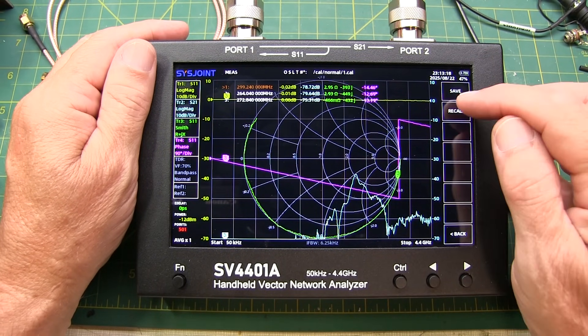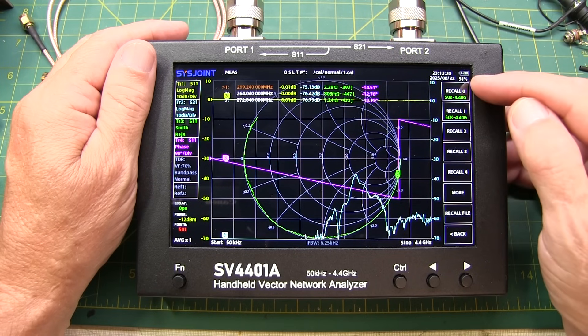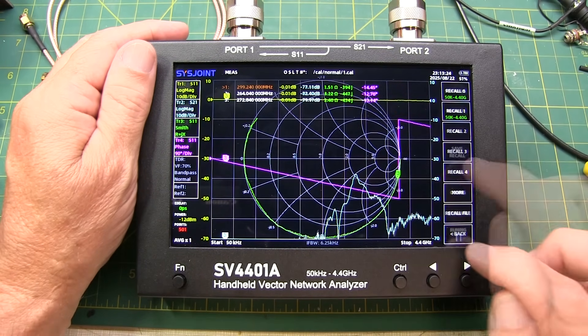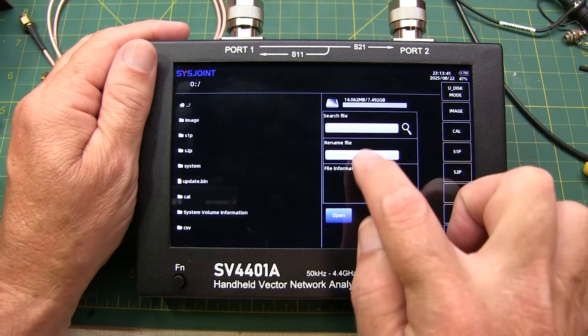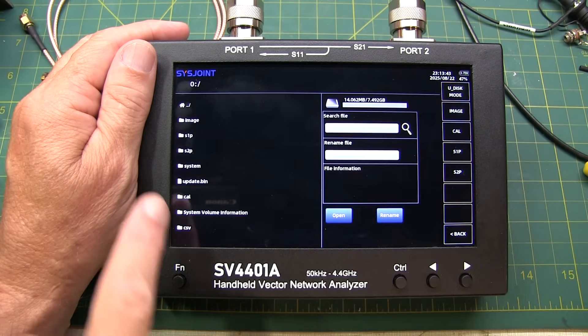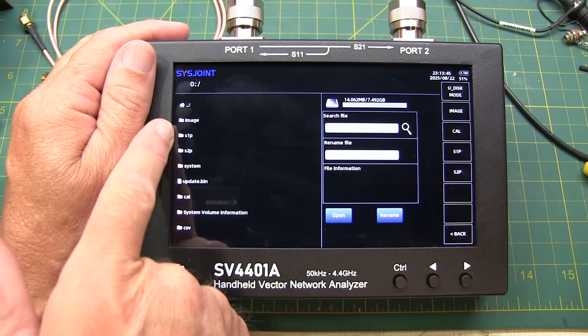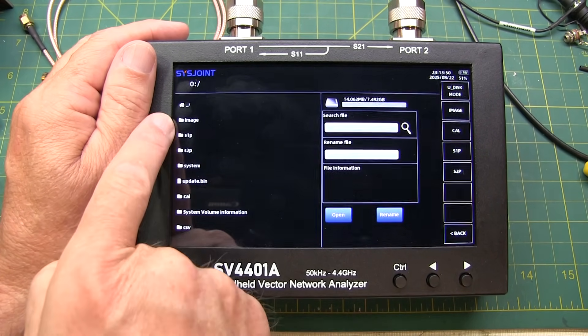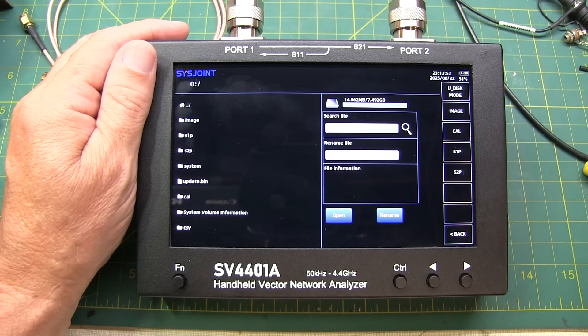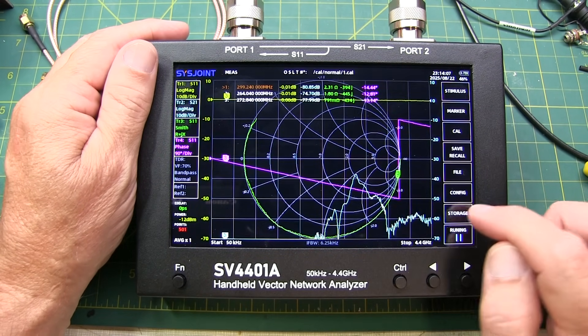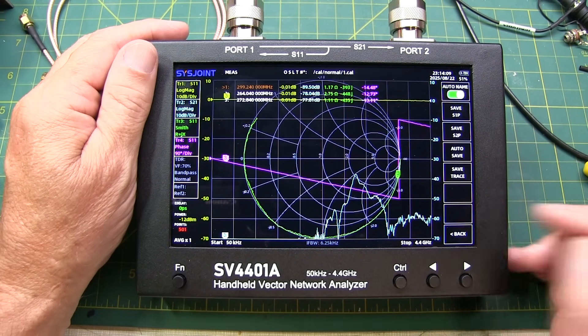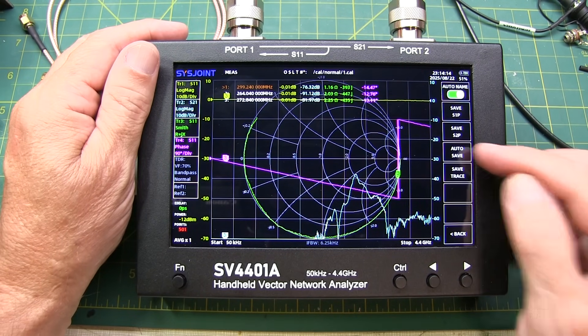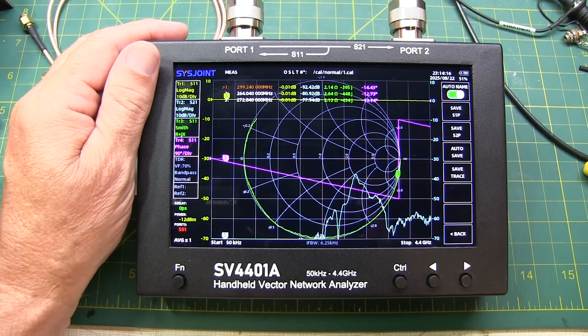The save and recall allows you to save and recall various settings, including calibration settings and things like that. The file menu allows you to go in and look at files that you may have stored, such as S-parameter files like S1P and S2P files, and even CSV files and image files that you can save on the instrument. And the saving of those files is all enabled through this storage button here. You can save the S1P, S2Ps, and also save traces as CSV files.